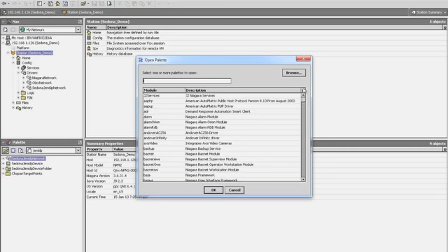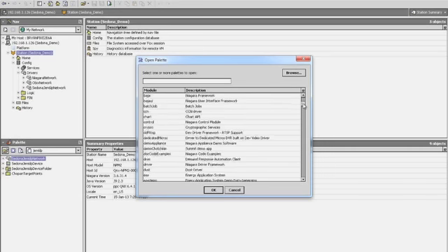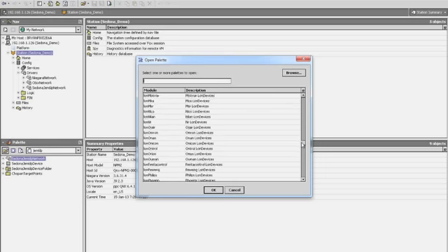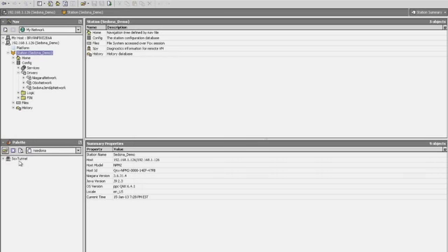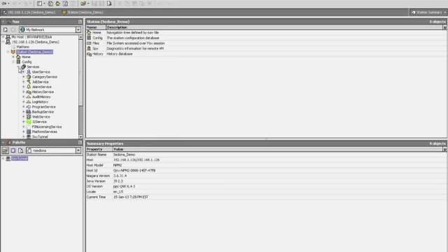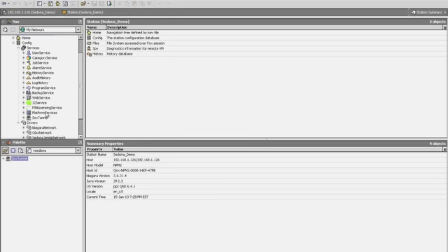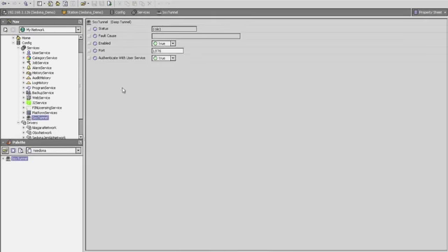So next we want to go look for the inSedona file. You scroll down to the inSedona and you see it here. And this is where your SOX tunnel service is located. In this case, we want to highlight it and drag and drop it over the services folder. Once it's there, go ahead and open your services folder and scroll down to your SOX tunnel service and open it. The very first thing you want to do is go to the last tab for Authenticate with User Service. Go ahead and set that to false.